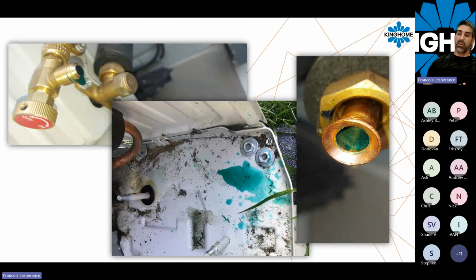Sometimes when you do a retrofit or work on a system, you might see some greenish or bluish oil coming out from the system. When you see that, it's really, really bad. That means the system operated with humidity inside of it. So you have an extra amount of moisture, and the system doesn't like moisture. It needs to be removed properly by the vacuum pump. But when it happens, you can see a discoloration of the oil, because the humidity and the copper, the inner portion of the pipe, will oxidize, and then that will affect the color of the oil.